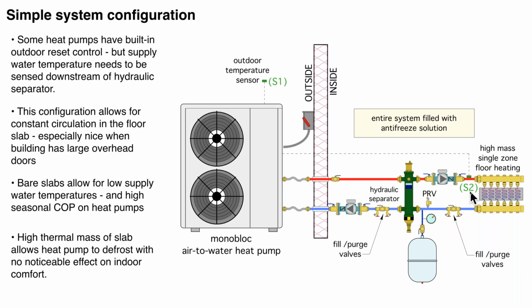There's no need for a buffer tank in there. It allows us to do constant circulation. The separator is giving us not only the hydraulic separation of these two circuits, but it's providing the air, dirt, and magnetic particle separation for us. Very simple. Again, I put a note here, because this is a monoblock heat pump, we're using antifreeze throughout the entire system.